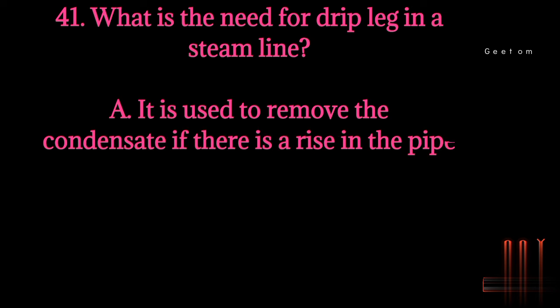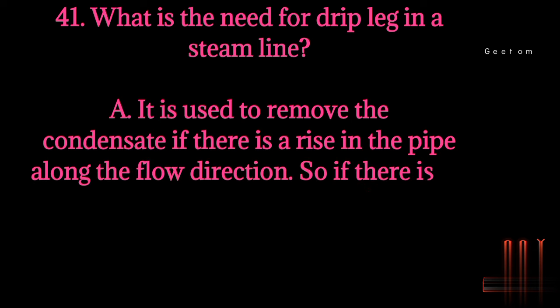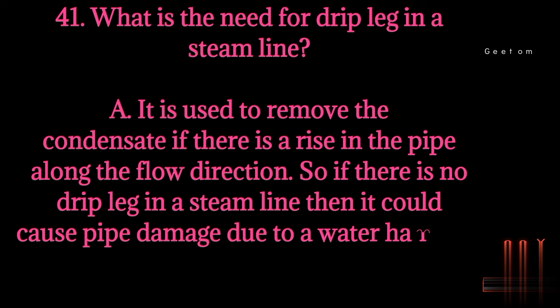Question 41: What is the need for drip leg in a steam line? Answer: It is used to remove the condensate if there is a rise in the pipe along the flow direction. If there is no drip leg in a steam line then it could cause pipe damage due to water hammer.